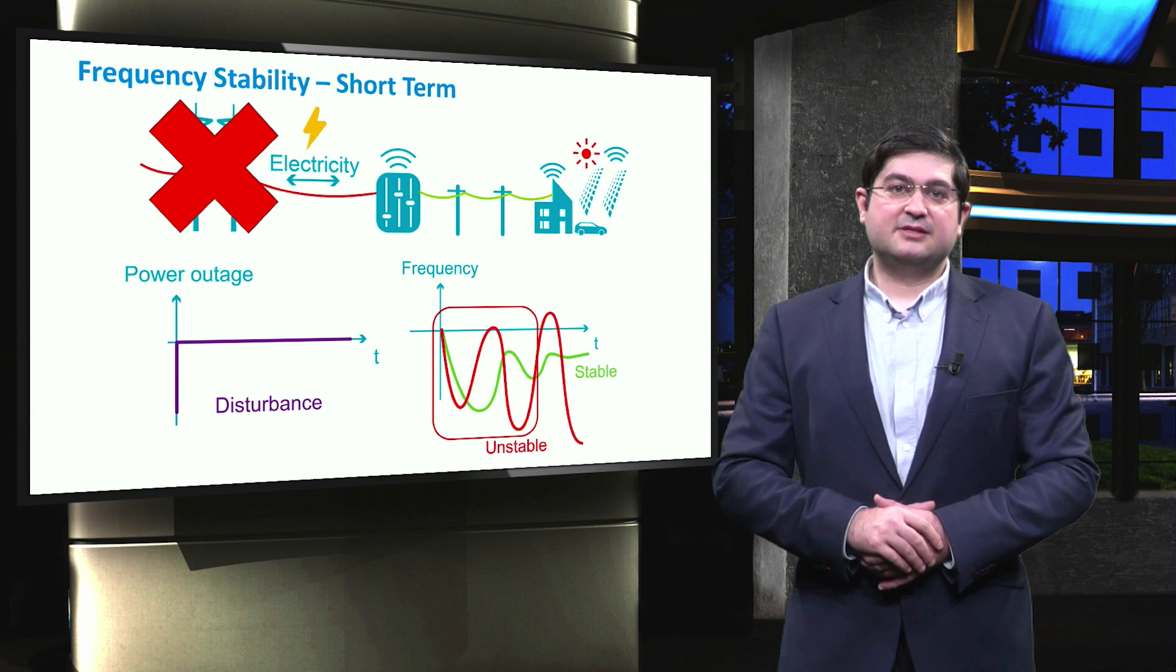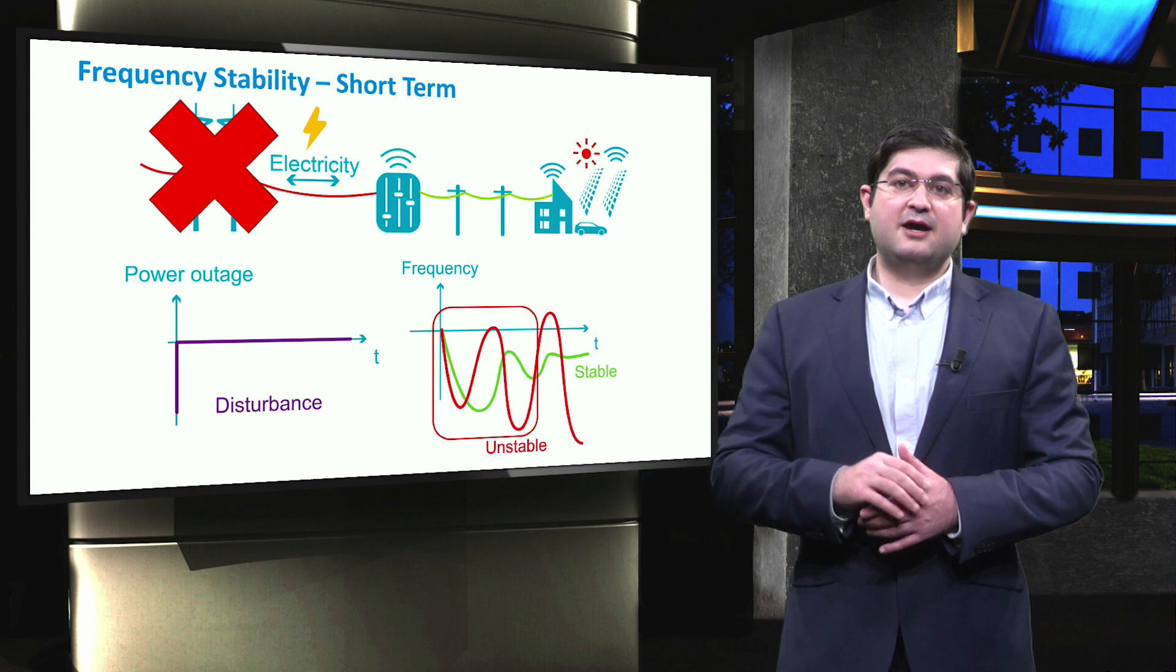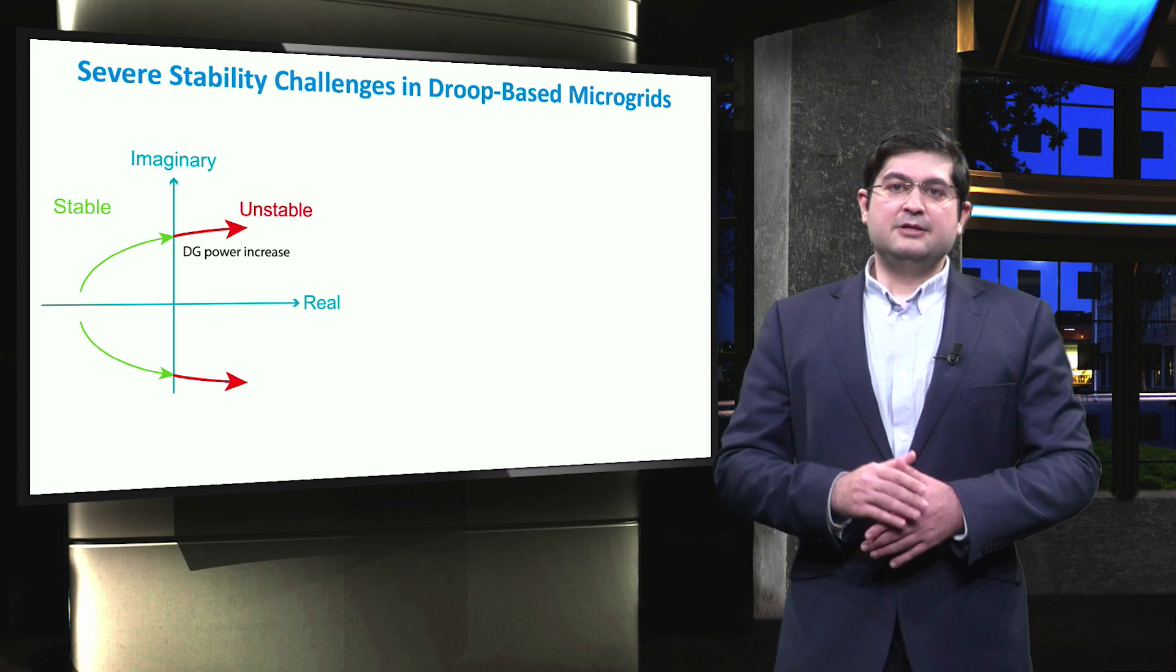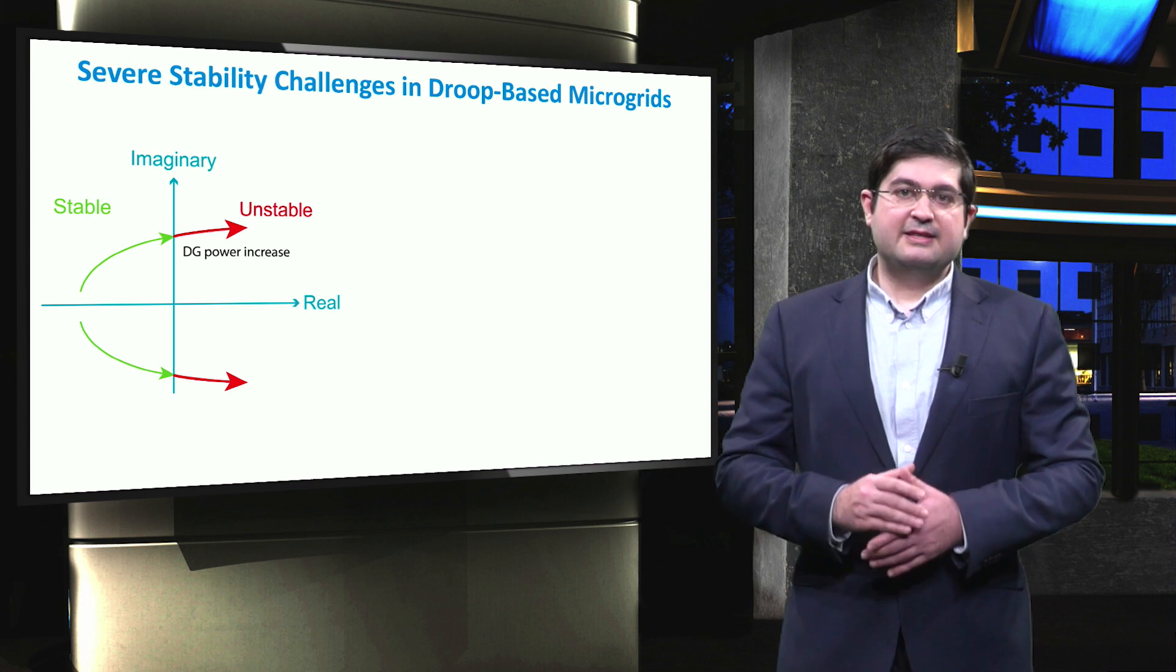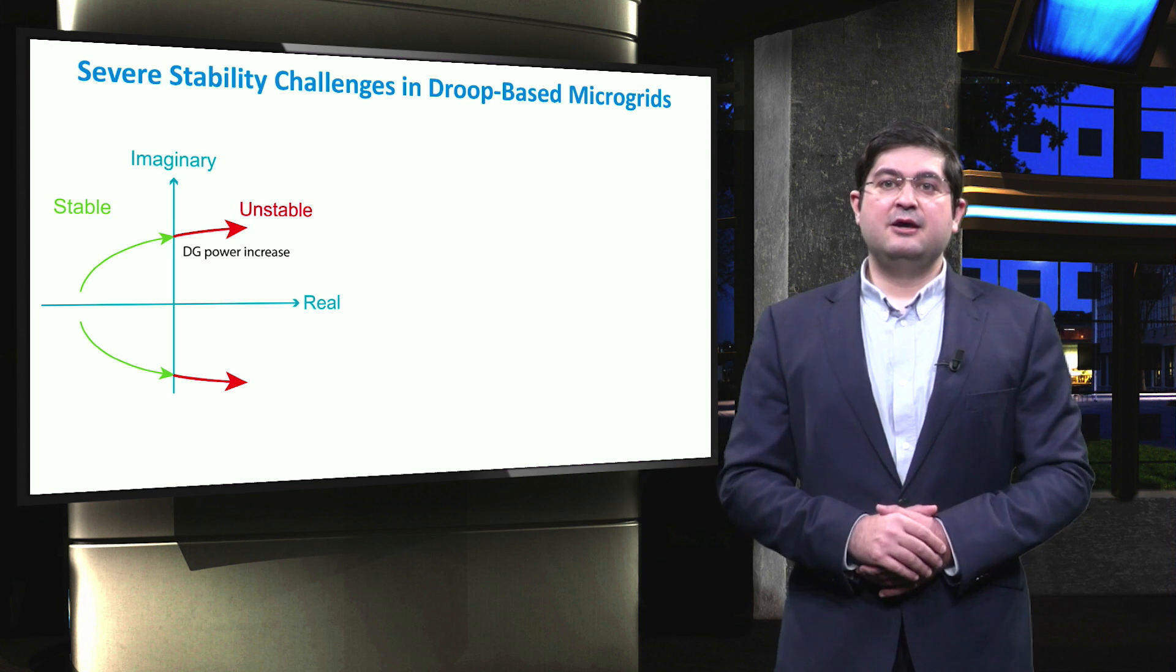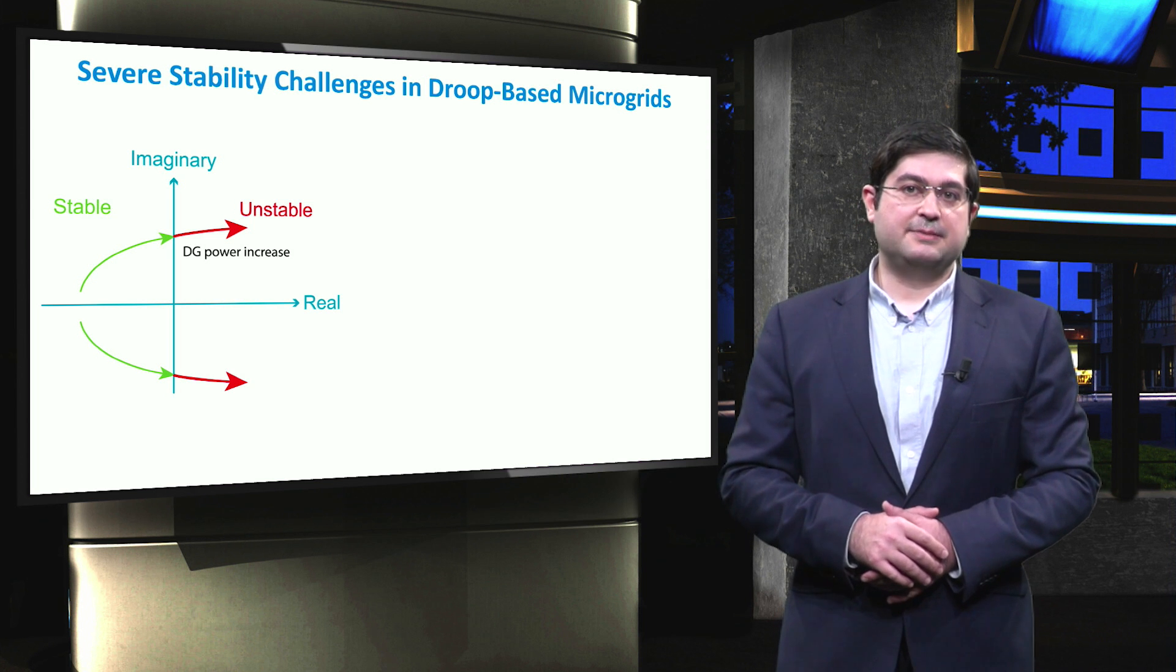If the frequency does not reach a stable point after the disturbance, then the islanded microgrid is shut down. Though the droop control is simple to implement, it has many disadvantages for droop-based microgrids such as poor transient performance or possible frequency instabilities.